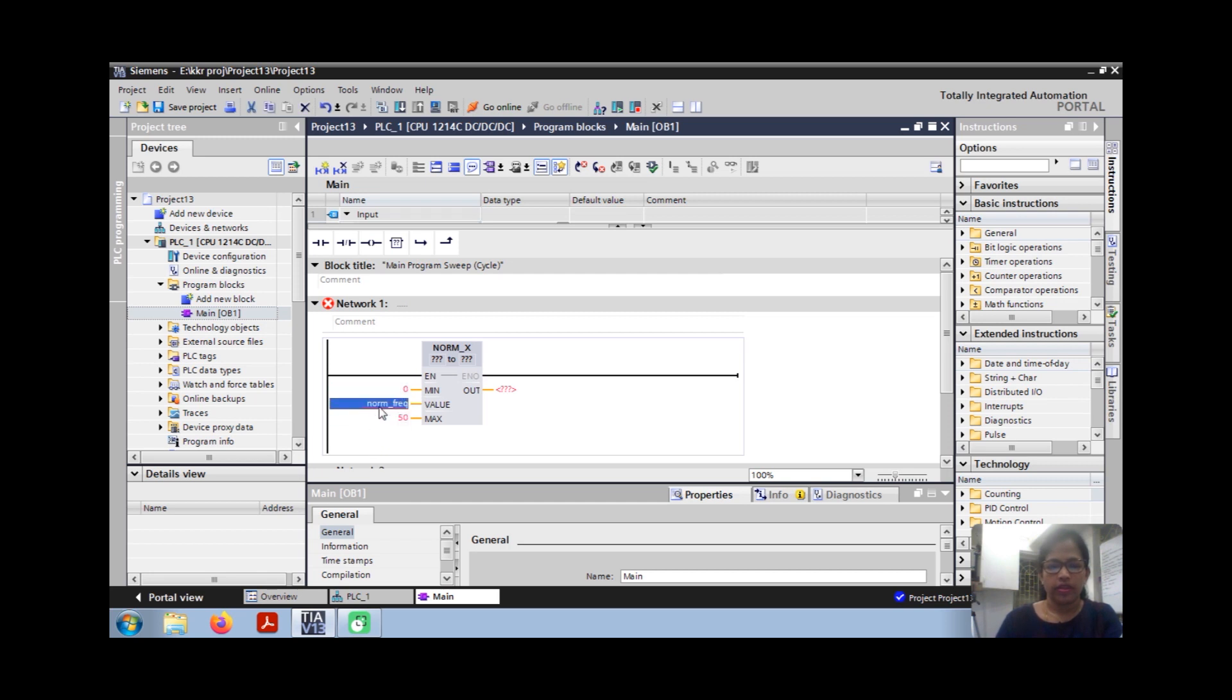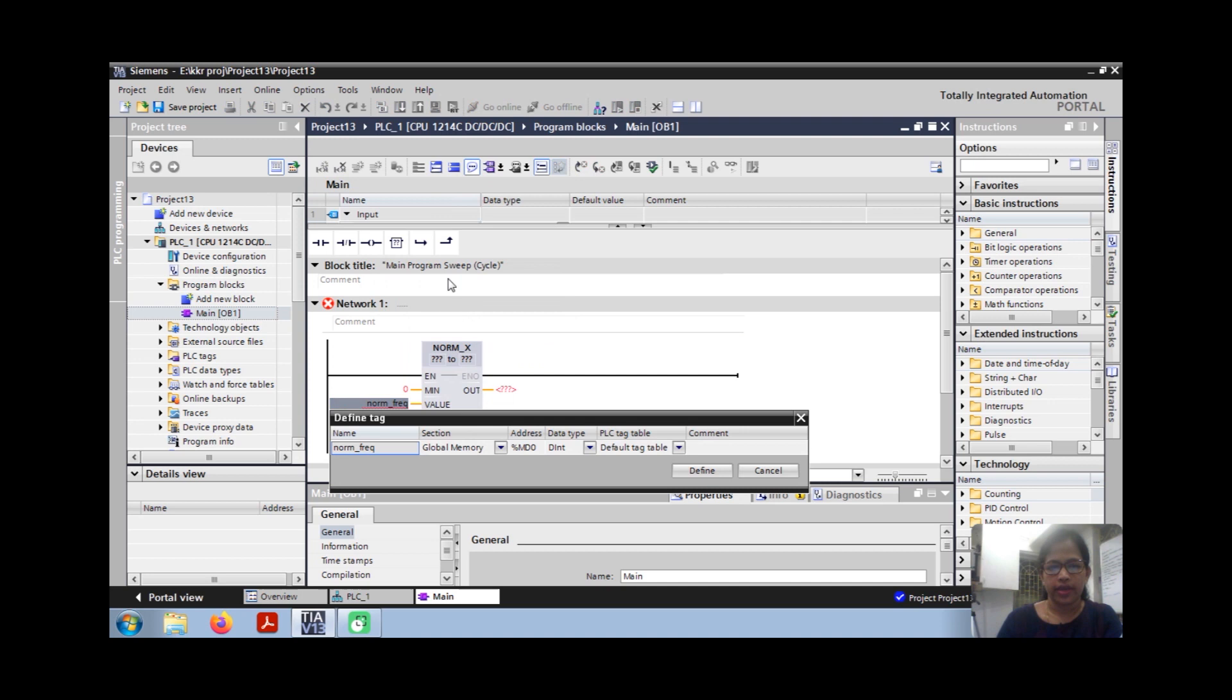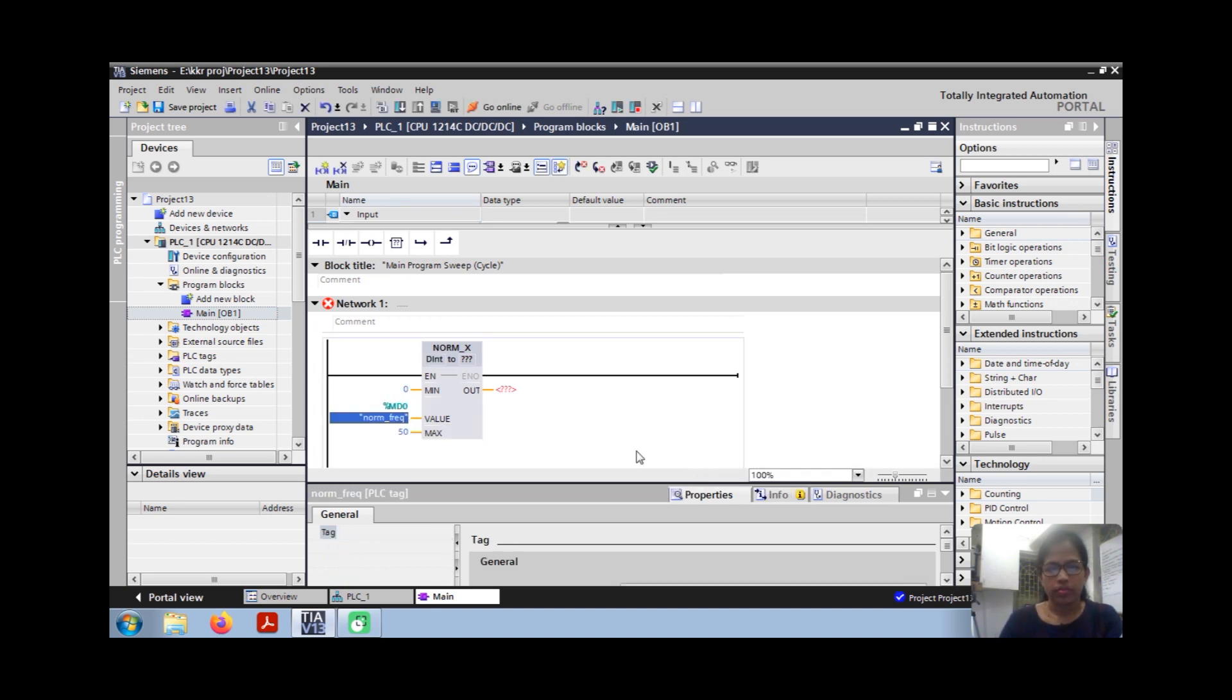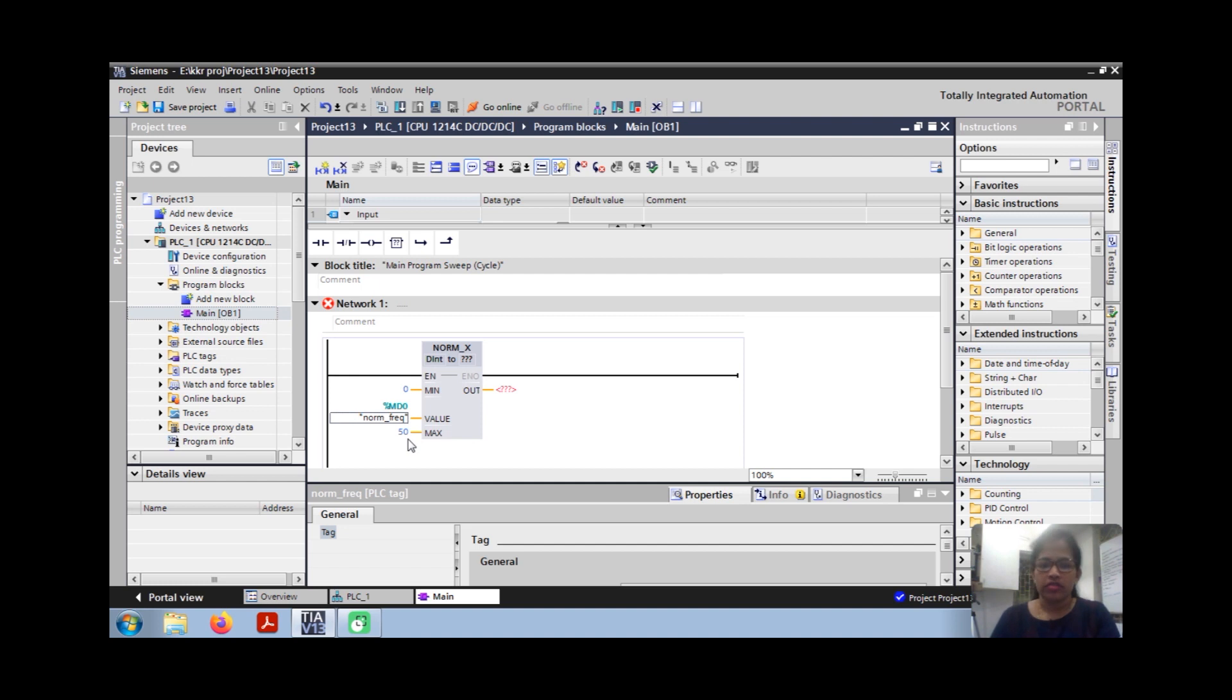Assign the tag, define the tag like this. Global memory MD0. So now the frequency is 0 to 50Hz I am going to assign. That is, normalize my 0 to 50Hz frequency to my tag. My tag resolution is 12-bit, that is 4096.